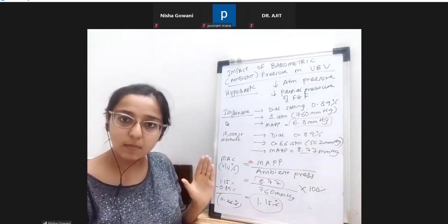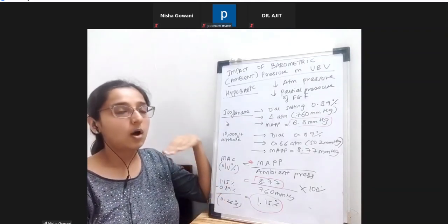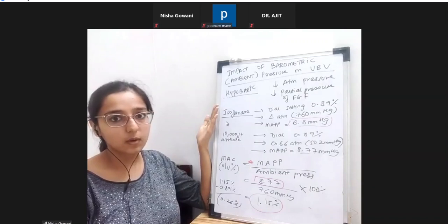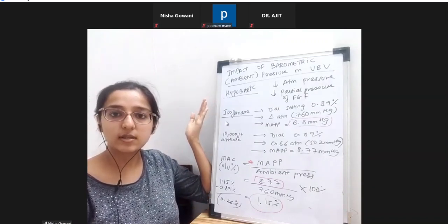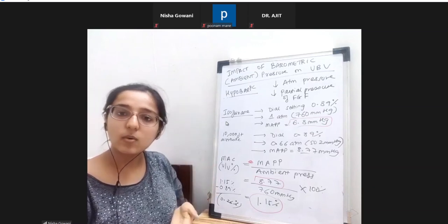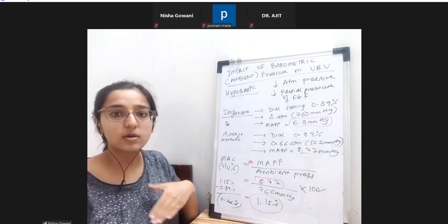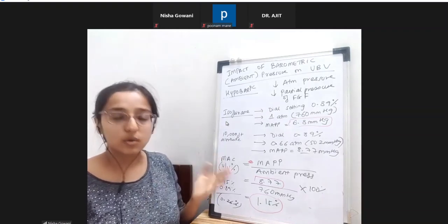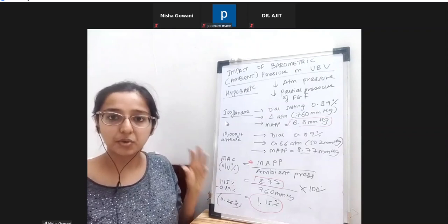So your take home message is that if you're using a variable bypass vaporizer on the mountains, maybe you're in Leh, Ladakh or somewhere, you have to conduct anesthesia there, or maybe you're down in a submarine somewhere, you have to conduct anesthesia there, or some different environment, you do not have to keep changing your concentration control dial. You set it as to what you want.